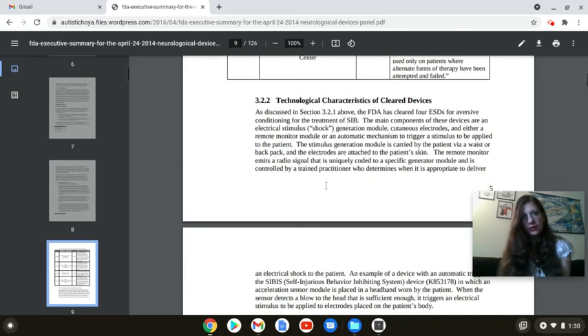Technical characteristics of cleared devices. As discussed in Section 3.2.1 above, the FDA has cleared 4 ESDs for aversive conditioning for the treatment of SIB. The main components of these devices are an electrical stimulus generation module, cutaneous electrodes, and either a remote monitor module or an automatic mechanism to trigger a stimulus to be applied to the patient. The stimulus generation module is carried by the patient via a waist or backpack, and the electrodes are attached to the patient's skin. The remote monitor emits a radio signal that is uniquely coded to a specific generator module and is controlled by a trained practitioner who determines when it's appropriate to deliver an electrical shock to a patient.